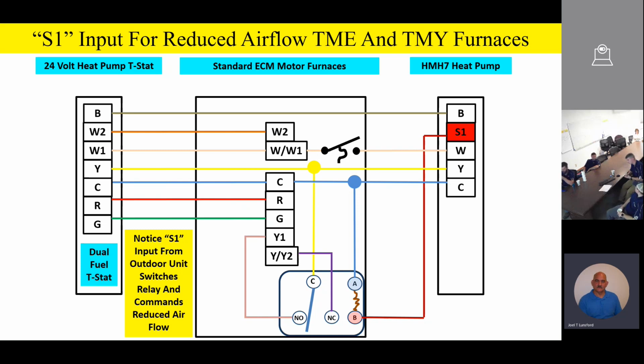Because the big thing about propane, you want to make sure that furnace comes up to speed and gets good and hot in between cycles. That way you don't corrode the heat exchanger. So that's all this is about. Number one, it's a comfort thing. But number two is to give us system reliability so we don't short cycle the furnace. That's what that's all about. Good question. Any other good questions or comments? Everybody good? Okay.